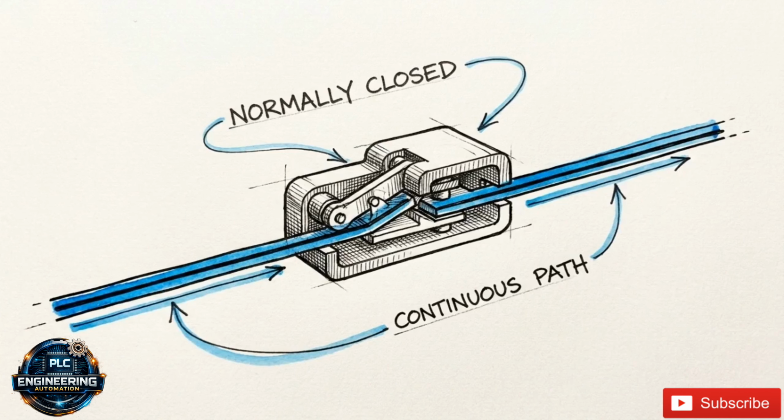If wired with a normally open contact, a severed wire leaves the circuit broken in the background. No one knows the damage exists until an emergency happens, the button is pressed, and the signal fails to reach the drive. Robust automation design assumes that components will break. By leveraging physical laws like the live zero and normally closed circuits, we guarantee that when a failure occurs, the system defaults entirely to a safe state.